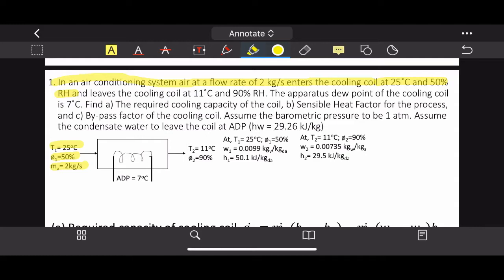State 2: air leaves the cooling coil at t2 = 11°C and 90% relative humidity. The apparatus dew point of the cooling coil brings the temperature even lower by forcing the air to reach saturation point, thereby reducing the temperature. The apparatus dew point temperature is 7°C.